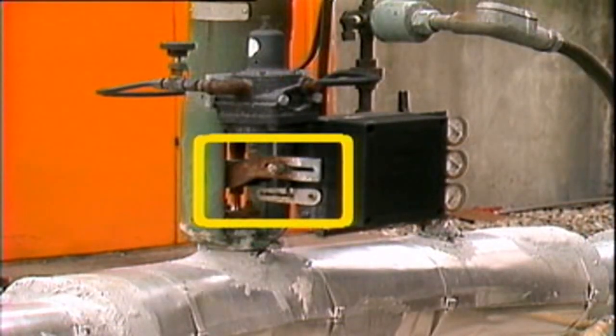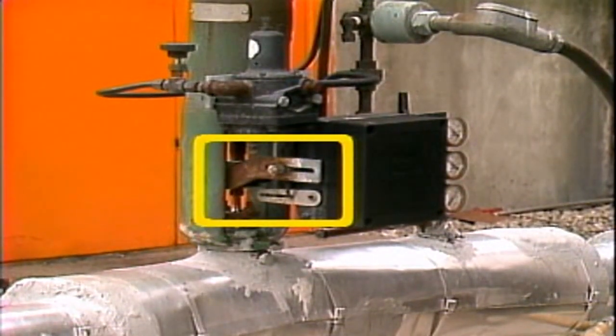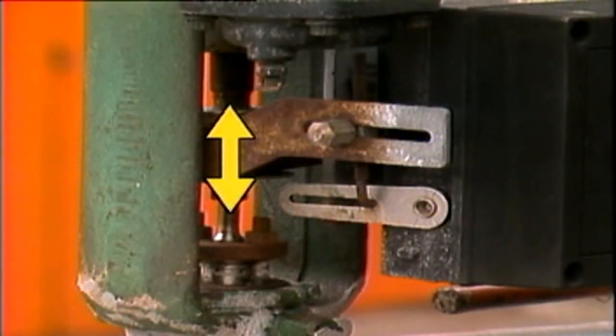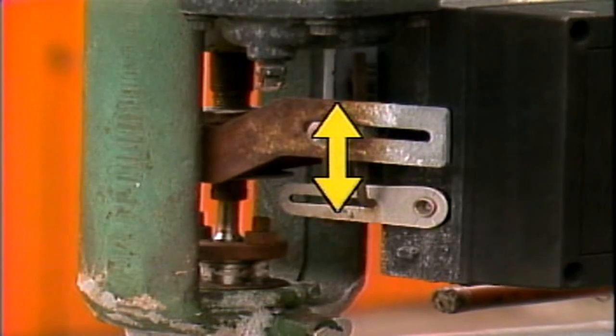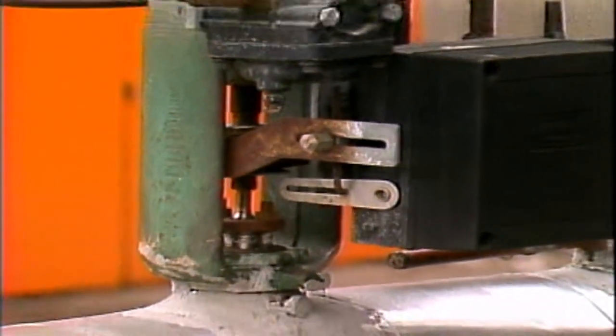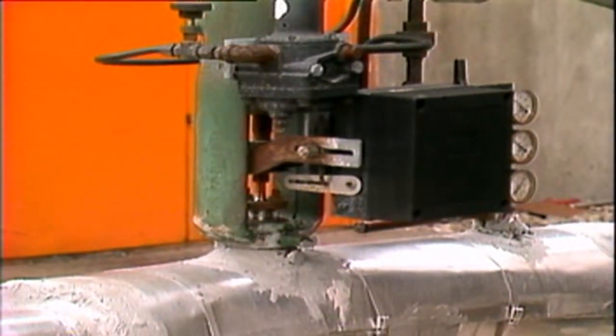A mechanical linkage joins the actuator stem to the positioner. This mechanical linkage may also be called a feedback linkage. As the actuator stem moves up or down, it also moves the linkage. The position of the linkage indicates to the positioner when enough movement has occurred to correspond with the air signal from the controller.